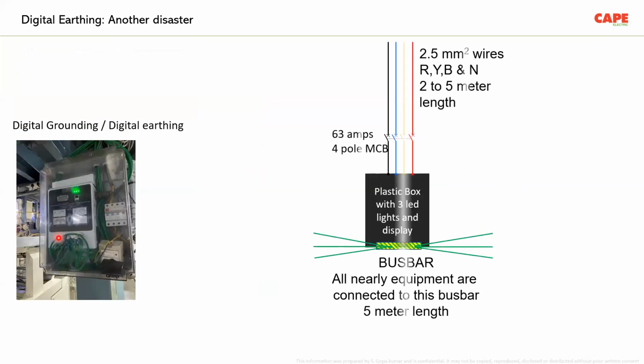So what we did is look at the box, which looks like this picture. It contains a black box. We don't know what exactly is inside. There are 2.5 square mm wires coming from the three phases and the neutral through a 63 amps 4-pole MCB. This is also not understood. How come a 63 amps MCB for 2.5 square millimeter wire? We don't know. Then there is a large bus bar, as I'm showing on this picture. I'm sure you are able to see the cursor. All the earth wires of nearby equipment are connected to this particular bus bar.